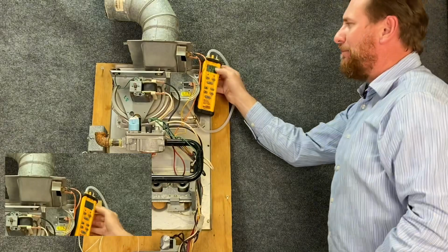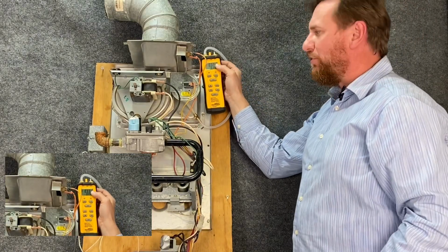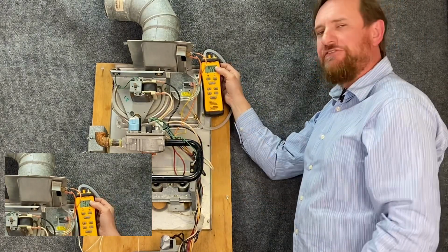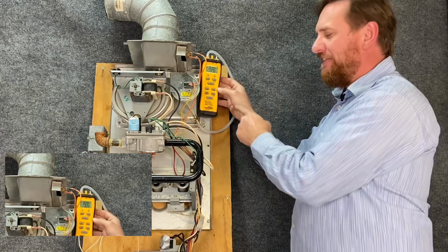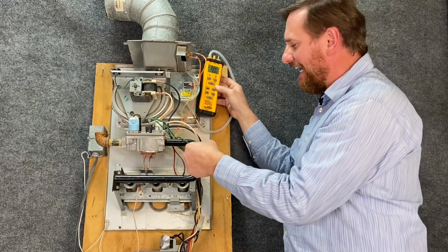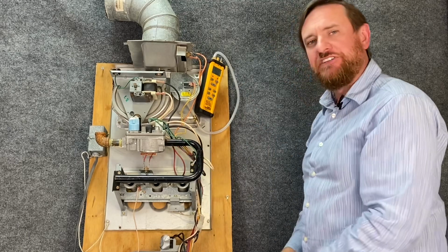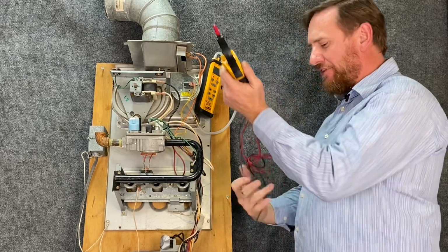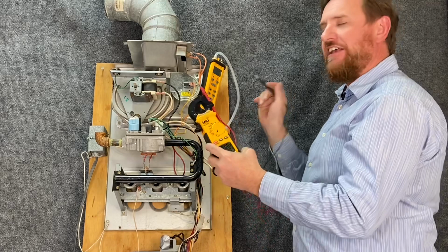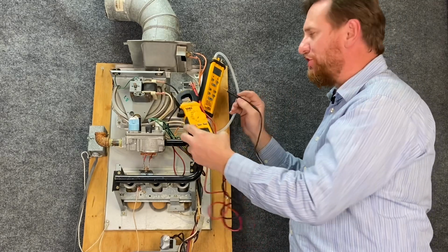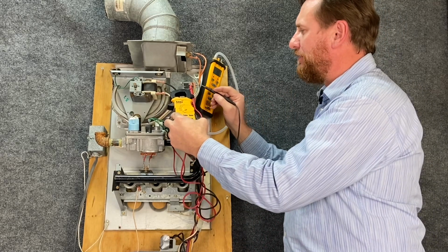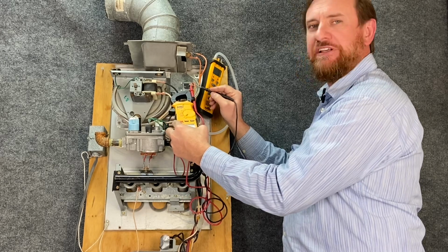Now we can see I'm pulling 0.34 inches of water column. It closes at 0.25. There's two ways I can now see if that's working. One way is I can look down and see if my hot surface igniter starts getting hot. The other thing I can do is check voltage. With the switch closed, I should have 0 volts. Put the meter on one side and then the other, I'm showing 0 volts.